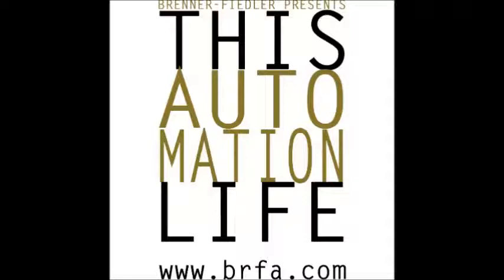And you can say, I'm going to basically linearize my overall system because it's repeatable. It's just not that accurate. Okay, so you'd program with some sort of an offset or something like that. Yeah, an offset or like a lookup table or something. Right. I can repeatedly go, when I go to 70 now, maybe I'm off by 2 degrees. But every time I go down to 60 and back up to 70, or up to 80 and back down to 70, I'm always off by 2 degrees.